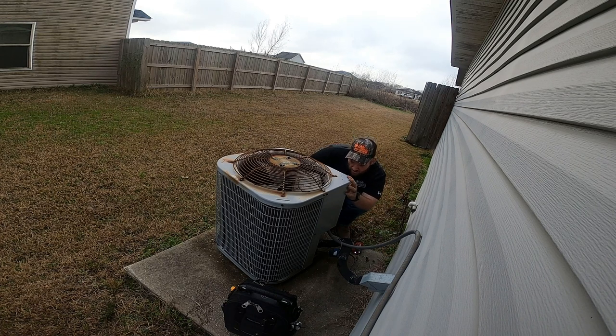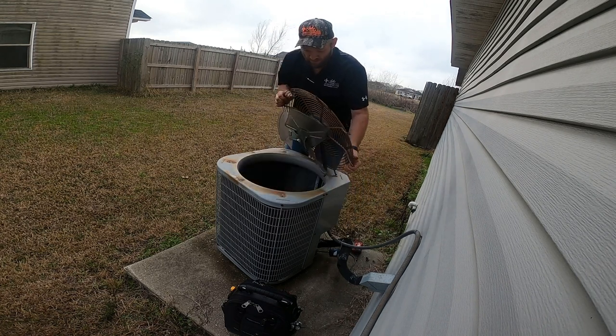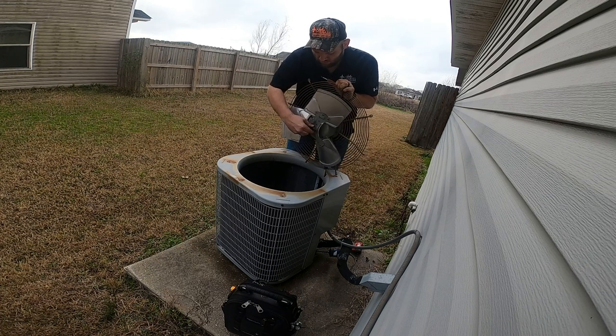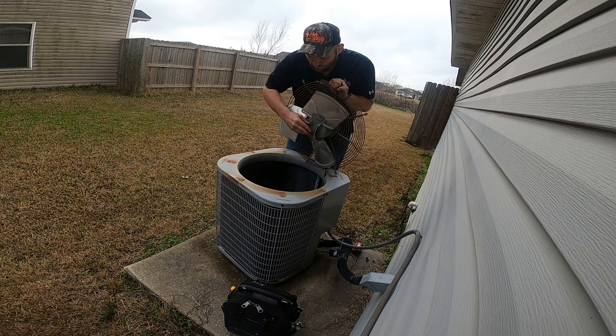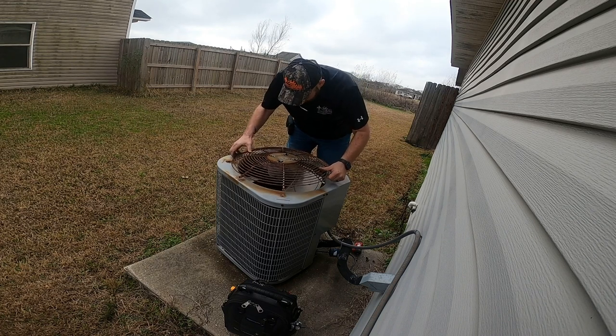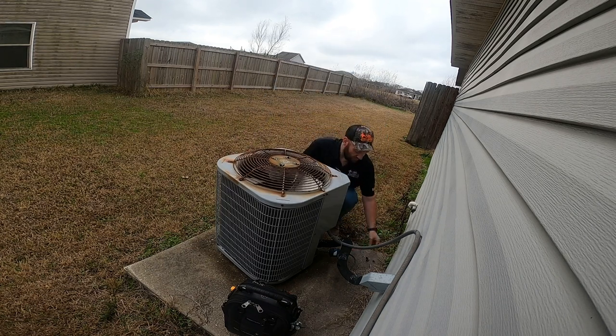13 SEER, two-and-a-half ton. I'm gonna bump it up to a three — oh yeah, there's a lot of slack in that shaft. There's slack. I mean, it's not out, it's still running, but it doesn't have a lot of life left in it.